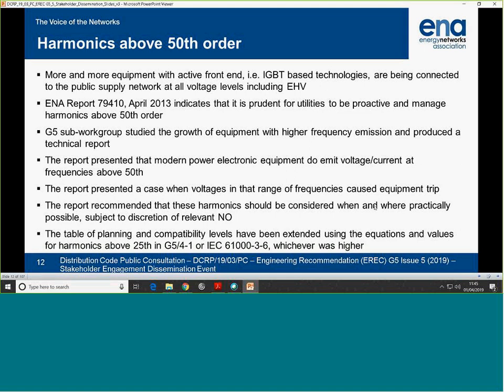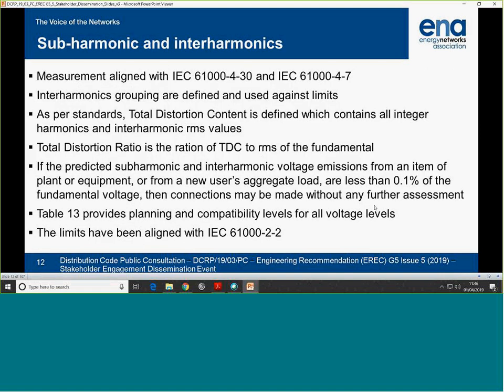For harmonics above 50, there are groups, as I said, in IEC and CIGRE working on that. But we chose just to extend the harmonic planning levels and compatibility levels from the 50th, there in G5/4, from 50th to 100. Harmonics and interharmonics. Measurement is very defined in G5. It's aligned with -4-30 and -4-7 for interharmonics measurements. So basically what it means here is that you can go and buy off-the-shelf monitors to do this for you.